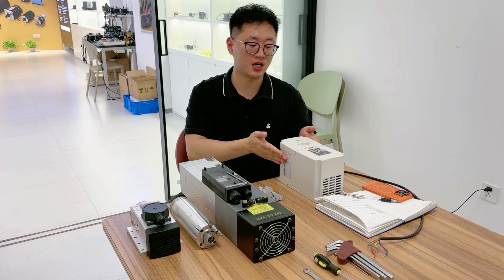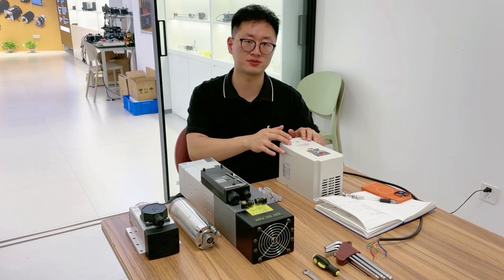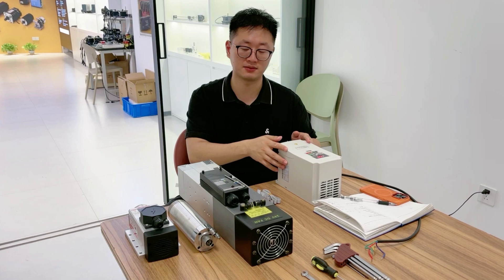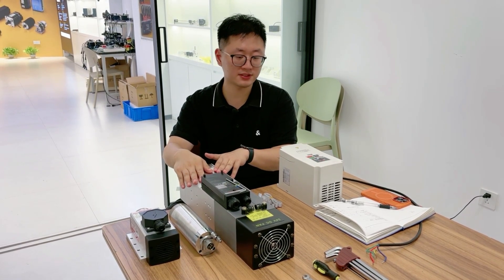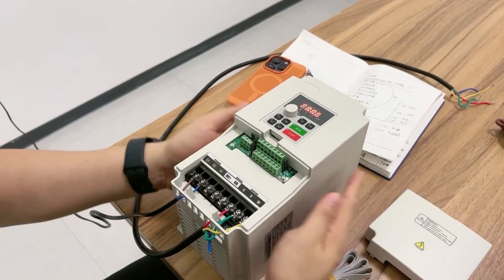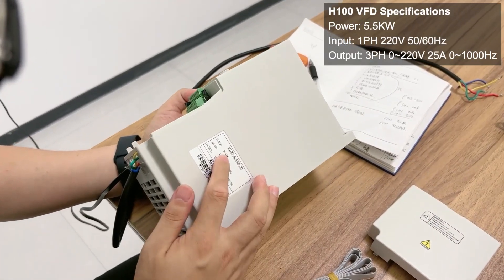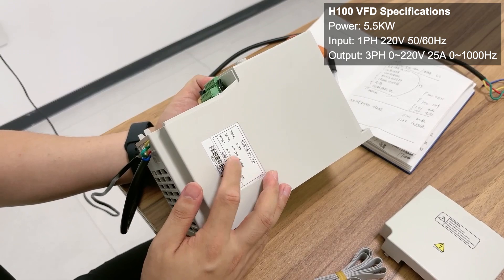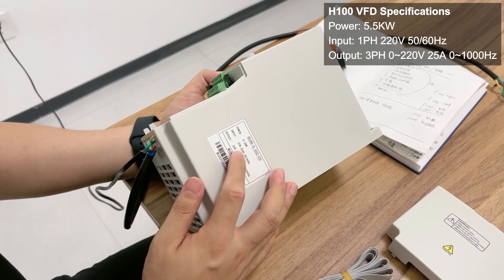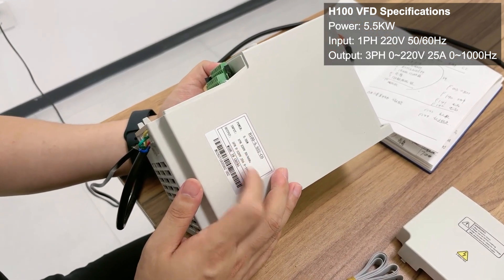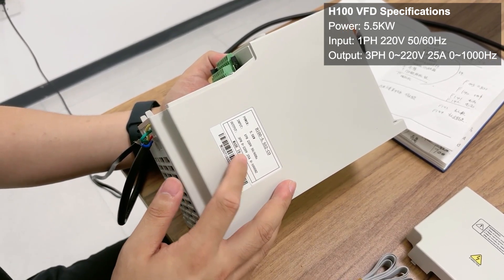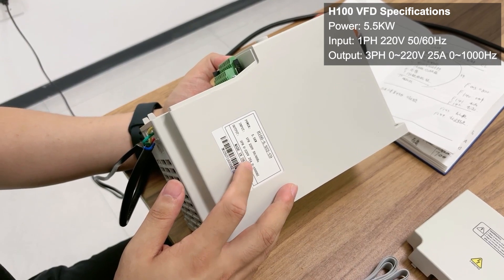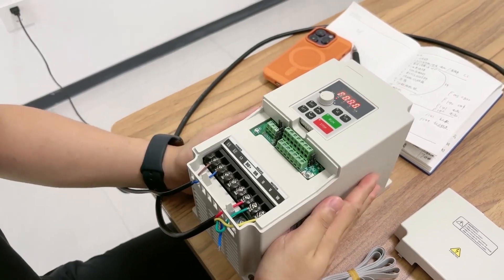Today I will teach you how to set the H100 parameters. Many parameters need to be set before running the spindle. First, come here. As you can see, this is the H100 VFD. This is a 5.5 kilowatt, single phase, 220 voltage unit. The output frequency is 0 to 1000 Hz. The current is 25A. And here are some main connectors we need to take seriously.